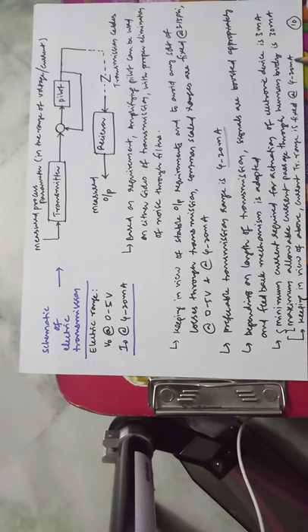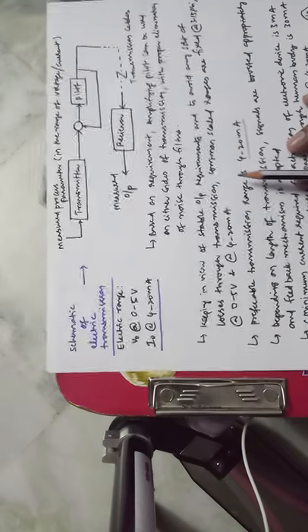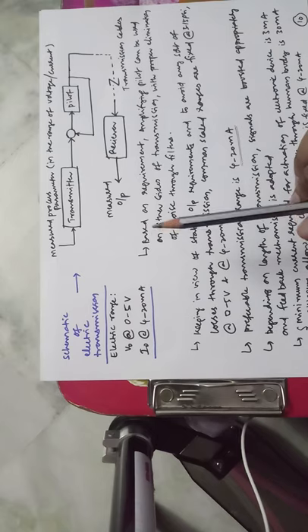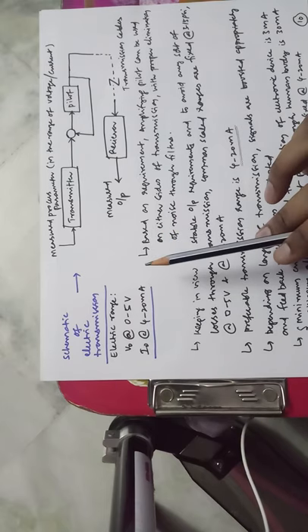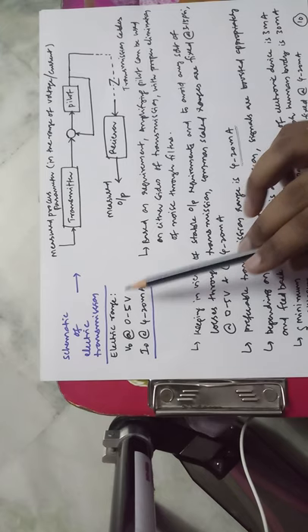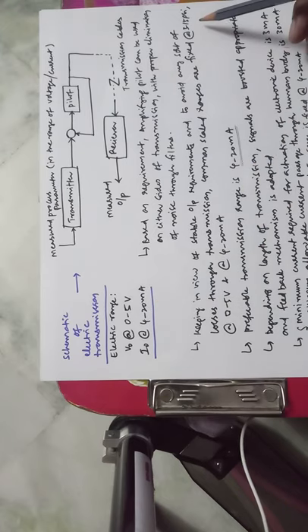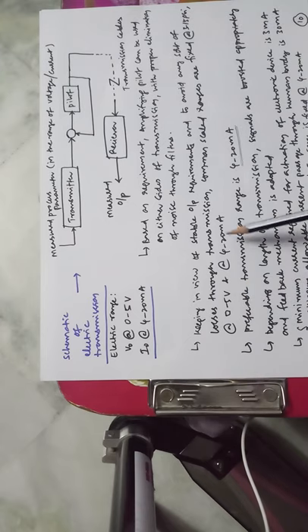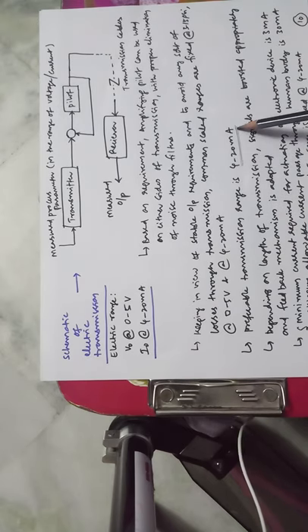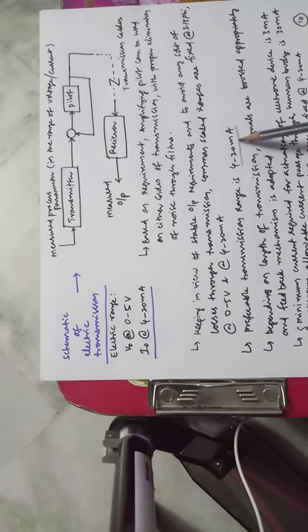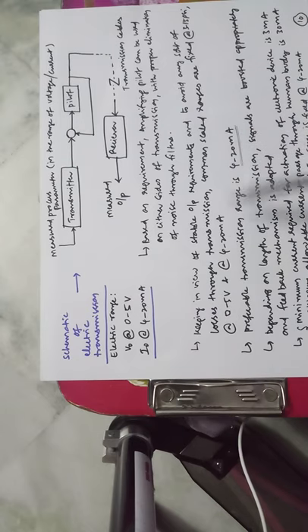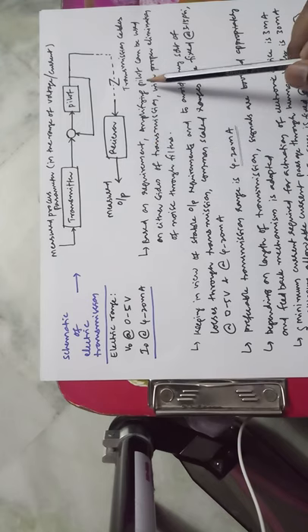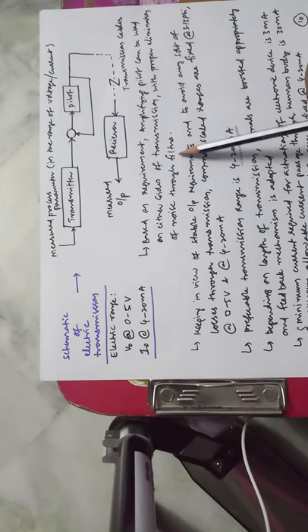To summarize: there are two types of systems — pneumatic and electrical transmission. In electrical, there are voltage and current transmission systems. The pneumatic range is 3 to 15 PSI, voltage is 0 to 5 volts, and current is 4 to 20 milliamps. The preferable range is 4 to 20 milliamps. Based on the requirement, amplification and noise elimination through filters must be adopted.